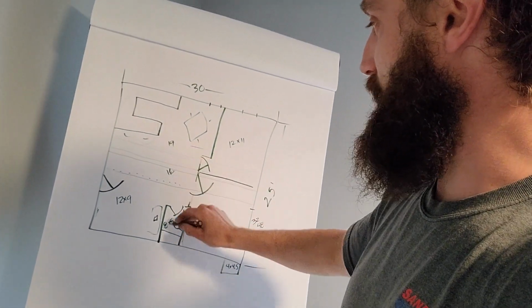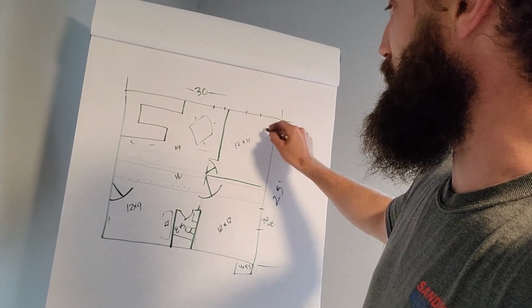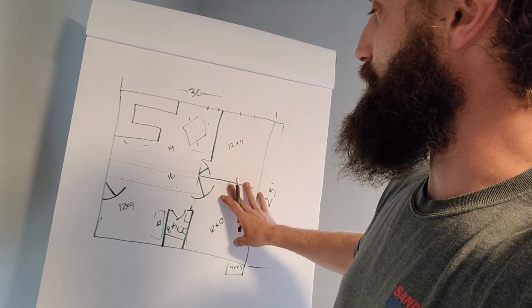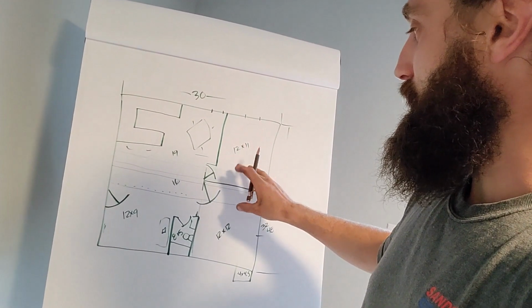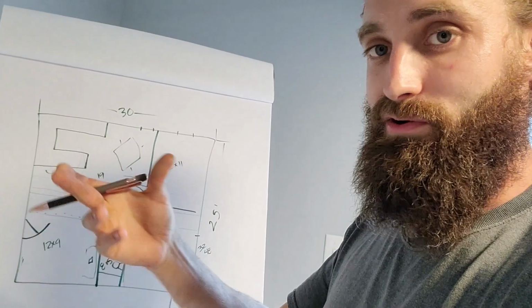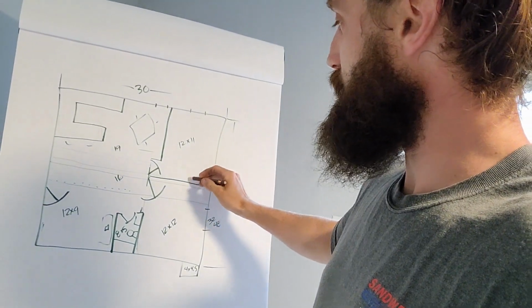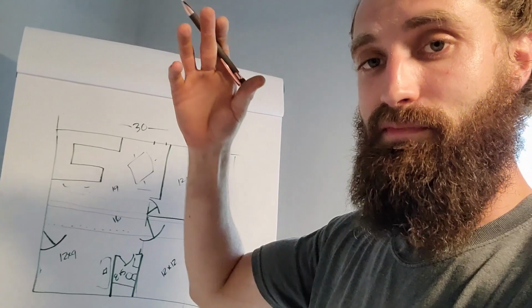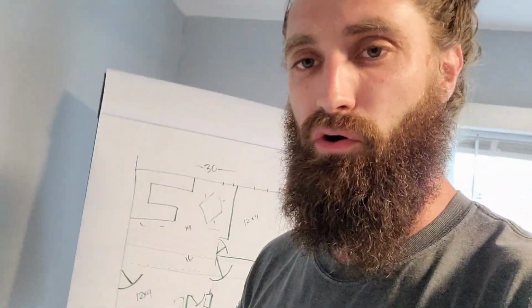take note of it, especially on an old floor like this, okay? Whenever you're dealing with an unconditioned crawl space below, it all needs to be accounted for. So that's pretty much the floors in a nutshell, okay? We want to, again, get the areas of the floor, know the materials on the floor, know how the floors are built, the thickness of the floor, if there's any insulation, and you're golden, okay? So once you've done that, then we're going to move to the ceilings, okay?